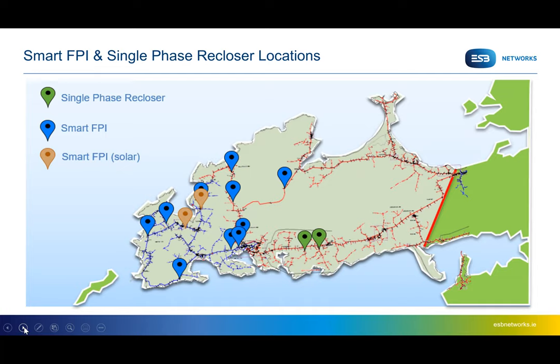So our trials of single-phase reclosers to date have been dumb elsewhere in the country, essentially with no visibility on our SCADA system or remote control enabled of those devices. So to view the history of what happened, you would have needed to visit the site and download data onto a laptop and all of this. And ultimately, where a permanent fault occurred and the device entered lockout mode, you still needed to send a technician to the site and operate the device either with a laptop or operating rods.